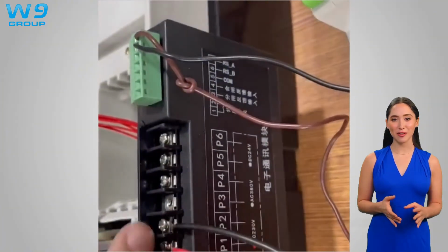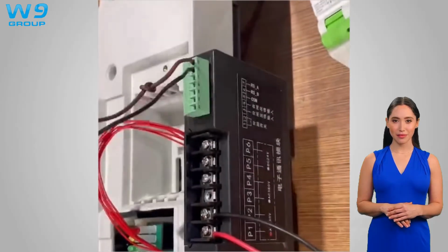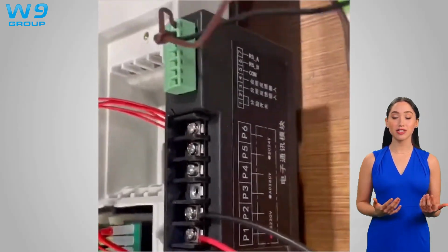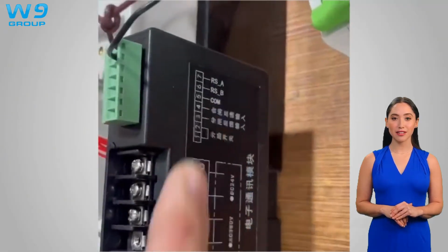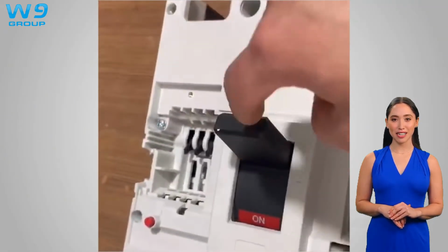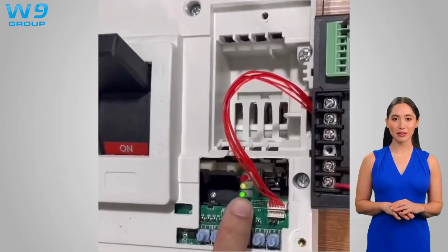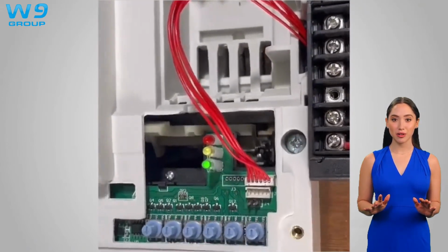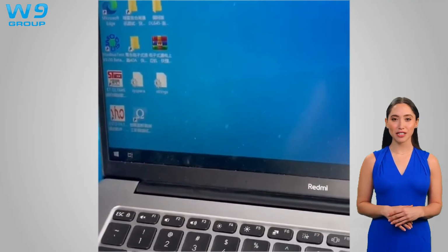After the device is powered on, we need to set the serial port number, baud rate, parity bit, and data bit. The setting of these parameters is crucial to ensure smooth communication. After the setup is complete, the serial port is open to start the communication. In read register address, by sending the corresponding command, we check whether the communication status is normal or not. In write register area, you can write the value to the specified register address. After completion, the communication status is checked again to ensure that the write operation is successful.